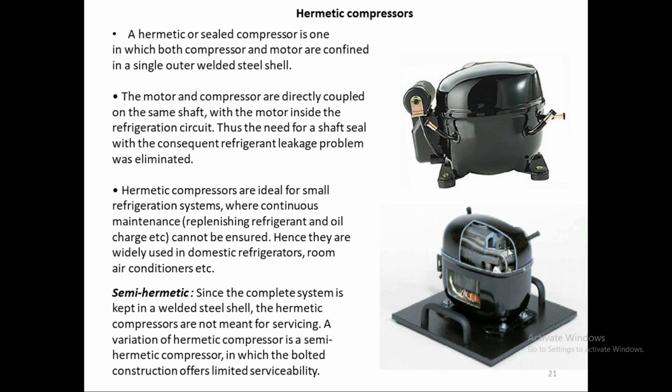The cutout is there. So here it is the compressor and the motor is this one. The compressor is here, somewhere here, and the positive displacement reciprocating compressor is here, and the motor is the down one. This is the stator, maybe this is the stator of that motor. Okay, the motor and the compressor are directly coupled on the same shaft, with the motor inside the refrigeration circuit. Thus the need for a shaft seal with the consequent refrigerant leakage problem was eliminated.